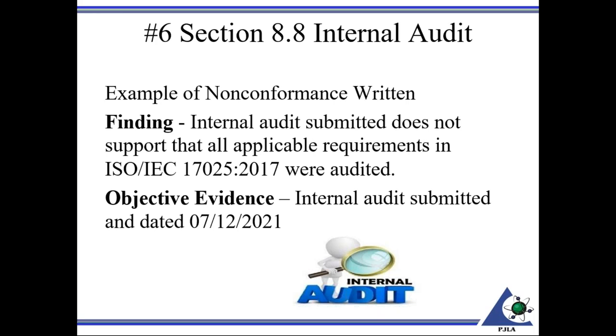So with this, you need to be auditing all applicable requirements and clauses, perhaps with an internal checklist. We have one available on our website that organizations will use to assure that you look at all applicable requirements. For example, 7.8, reporting the results. If 7.8 applies to you, there should be objective evidence that your internal audit incorporated auditing the reports that you produced. Corrective action, that you're auditing the corrective actions that were performed by the organization, to ensure all required elements were met.